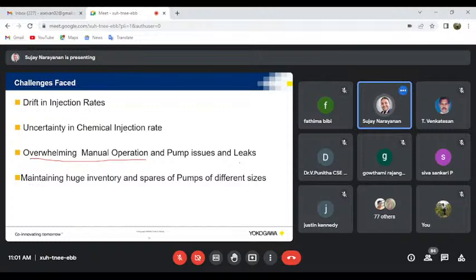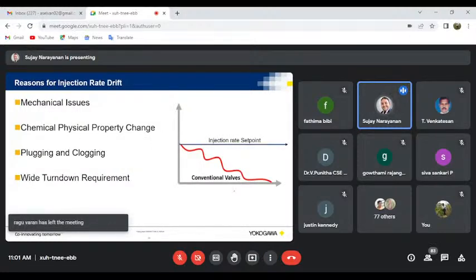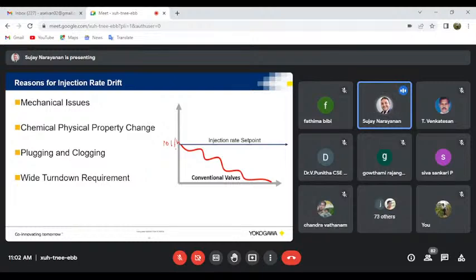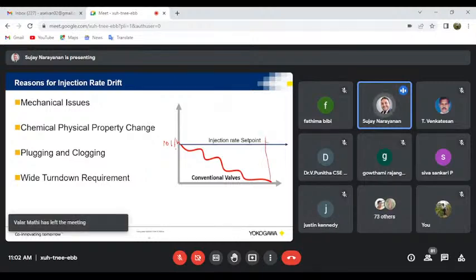Pump issues and leaks, and maintaining huge inventories and spares of pumps of different sizes. What I mean by injection rate is, let's say the set point is 10 liters per hour. If you put a set point of 10 liters per hour, it is expected that the pump should hold at 10 liters per hour, plus or minus 0.2 is okay. But the pump drifts like this. Somebody has to go and correct it. Once it's drifting, somebody needs to set it again. Again, it will drift. So this is why this happens.